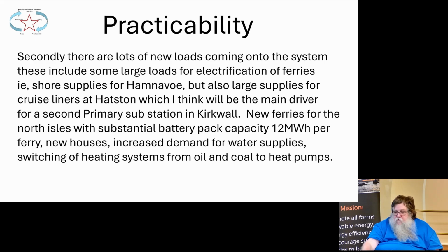And then the second reason is there's lots of new loads coming onto the system. We've got some new large loads for electrification of ferries, like the shore supplies for Hamnavoe. There's potential for shore supplies for 3 new North Isles ferries, which, when I went along to the consultation events, the battery pack capacity could be 12 megawatt hours per boat. So if you look at that and say they're not going to use it all every day, but maybe 8 megawatt hours out of 12, they're going to need a 1 megawatt supply each night to recharge the batteries, each boat. So that's 3 megawatts.